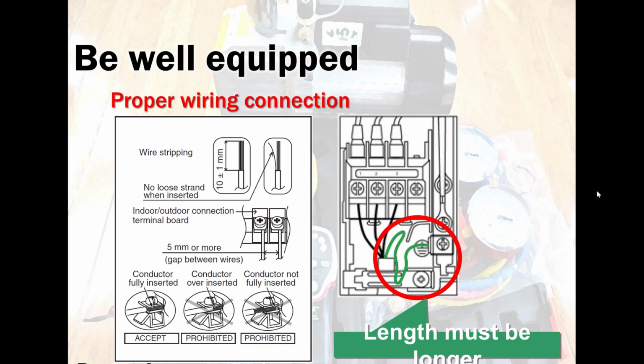After a week or so, you get a call. Oh, are you joking? I said, I'm telling you. And right enough, they called me back and said, yes, I had to go back to that house. They called me H11 error code. Because that wire between indoor and outdoor is constantly talking. They are constantly talking between indoor and outdoor to get that communication protocol going. And when you put a joint, you're creating some kind of resistance, interruption, noise, disturbance, and that causes H11 error code. Because when there is a split second of miscommunication, the system shuts down.